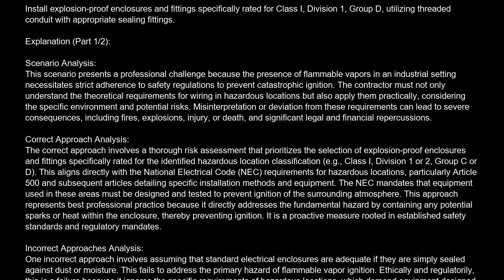The NEC mandates that equipment used in these areas must be designed and tested to prevent ignition of the surrounding atmosphere. This approach represents best professional practice because it directly addresses the fundamental hazard by containing any potential sparks or heat within the enclosure, thereby preventing ignition. It is a proactive measure rooted in established safety standards and regulatory mandates.